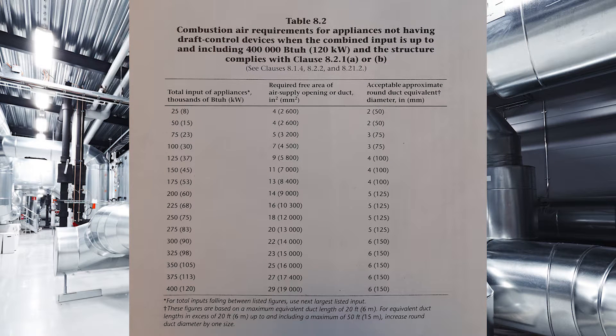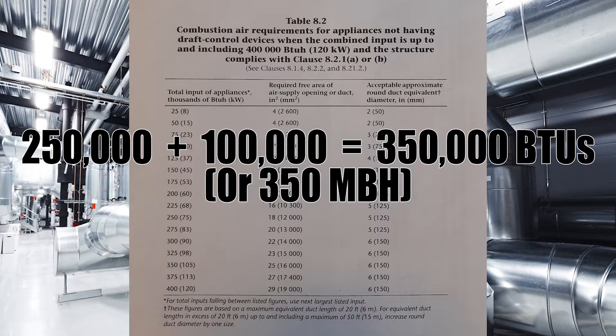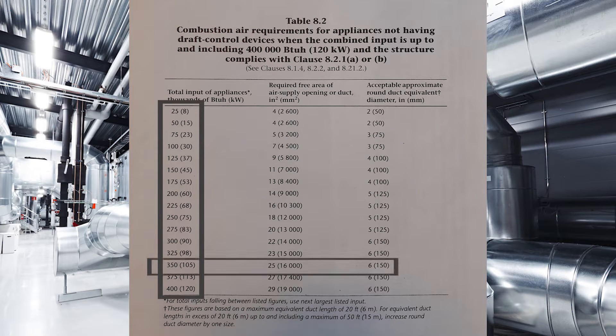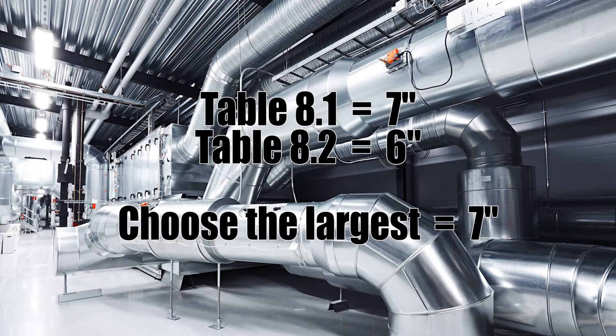Now we look at table 8-2 with a combined total of everything. I've got a 250,000 BTU boiler and a 100,000 BTU furnace — put those together and I've got 350,000 BTUs. I go down to 350,000 BTUs on the left-hand column, come across to the right, and I need a 6-inch round air supply. Now I need to choose the larger one. Table 8-1 said 7 inches, so 7 inches will be my air supply size.